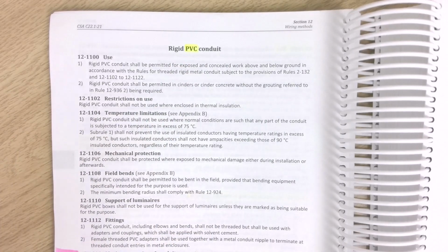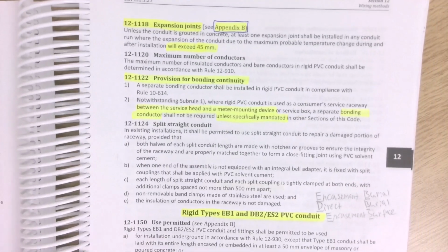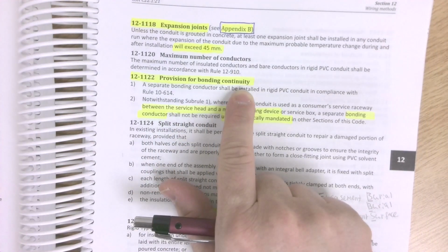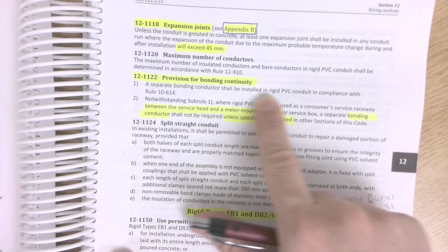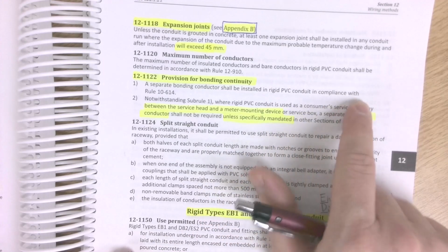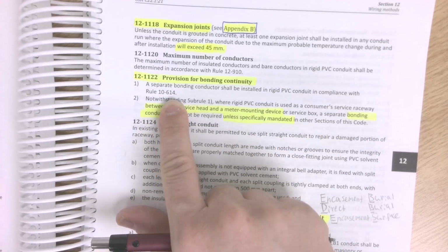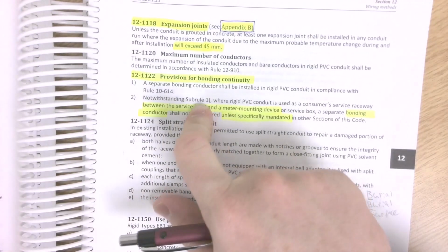And I'm looking for this phrase, provision for bonding continuity. And it's going to say that a separate bonding conductor shall be installed in a rigid PVC conduit in compliance with Rule 10-614.